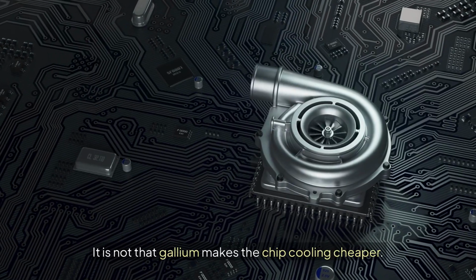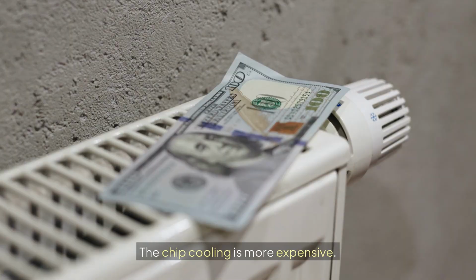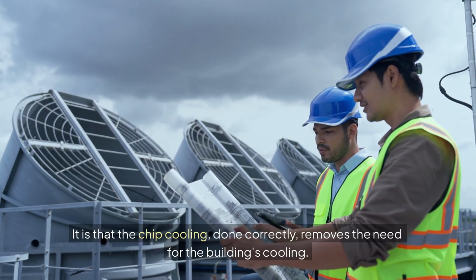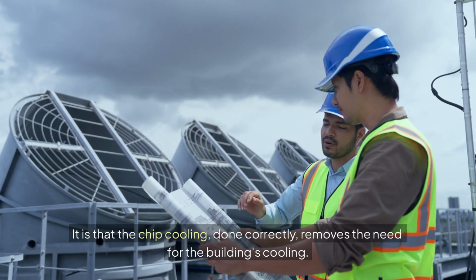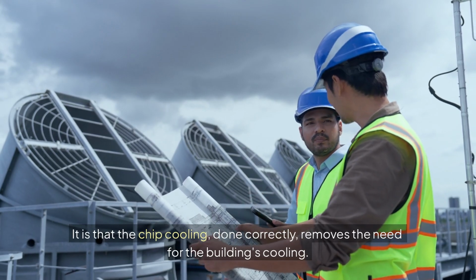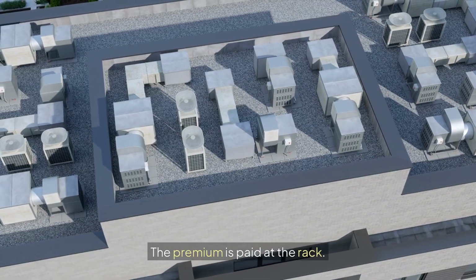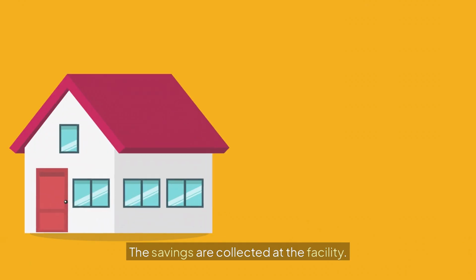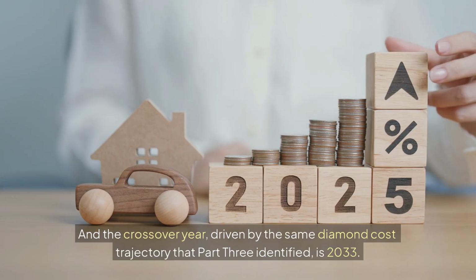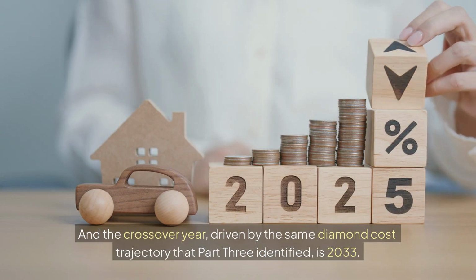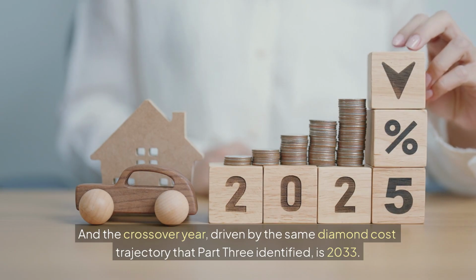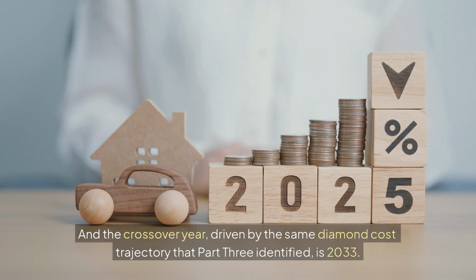It is not that gallium makes the chip cooling cheaper. The chip cooling is more expensive. It is that the chip cooling, done correctly, removes the need for the building's cooling. The premium is paid at the rack. The savings are collected at the facility. And the crossover year, driven by the same diamond cost trajectory that Part 3 identified, is 2033.